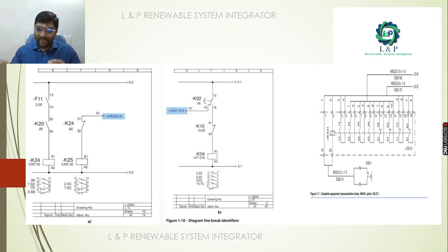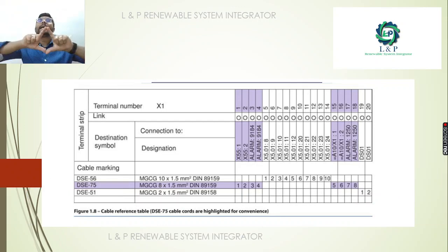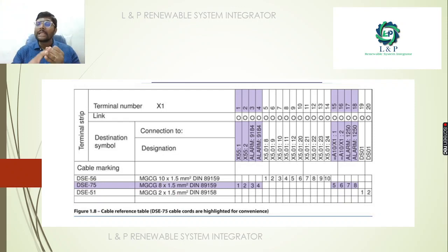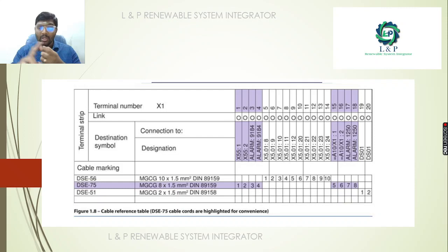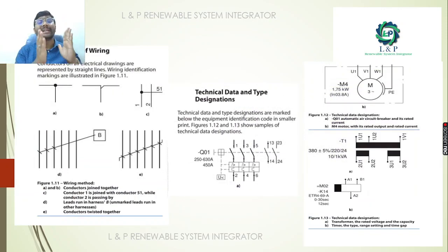Here is an example of complete equipment representation — whether it's a relay or a plant — and how to represent it. Next, we need to draw a cable reference table, which is very important. We need to highlight the cable cores, mention the terminal number, link to destination symbol showing where we are connecting, cable marking, and cable size. All these things need to be mentioned in the cable reference table.